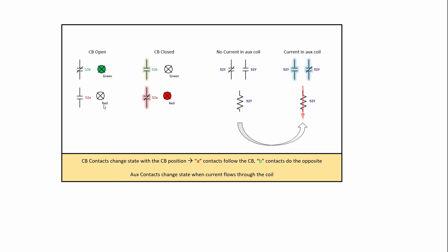52A follows the breaker. 52B does the opposite of the breaker. And then later on my diagrams, if they're in their opposite state, I have them highlighted like that. Aux coils, like this case, a 52Y, are shown in the de-energized state. And then when you put current through them or voltage across the coil, they change states. And again, I'll have them highlighted like that.